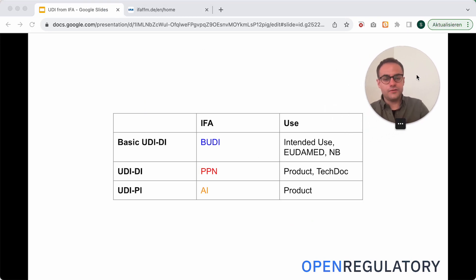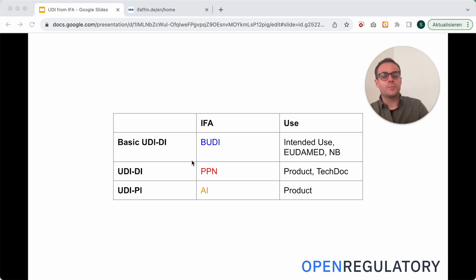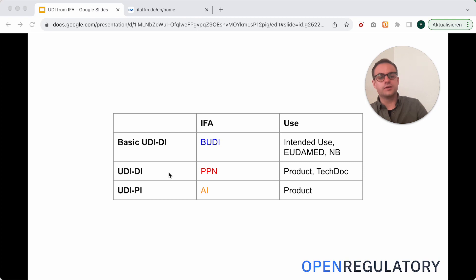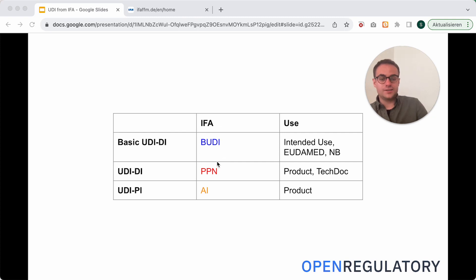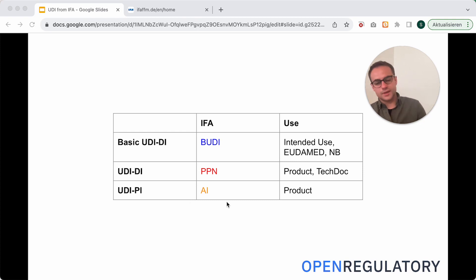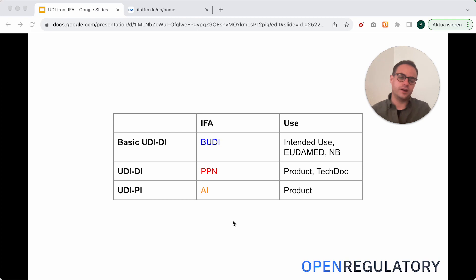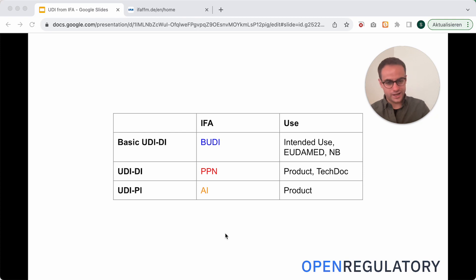How do those IFA numbers translate to UDIs? IFA issues PPNs, and those are your UDI-DIs. Those change for every major version update of your software. IFA also generates B-UDIs — that's the basic UDI. The UDI-PI system follows rules of the application identifiers from IFA, and that one you can just make up yourself — you can be very creative there.